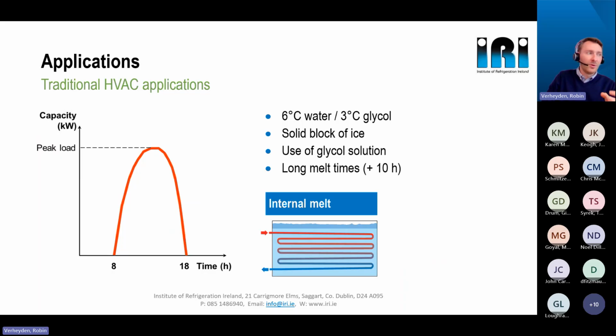Now, let's take a look at a typical HVAC application. It has a quite small increasing load with a long meltout time, between 8 and 18, so 10 hours, and typical water temperatures on the water side of 6 to 11 degrees. On the glycol side, the other loop of the heat exchanger, typically 3 degrees, for example. That means the perfect solution here would be internal melt, a closed circuit, so we use the same coil to build as to melt the ice.